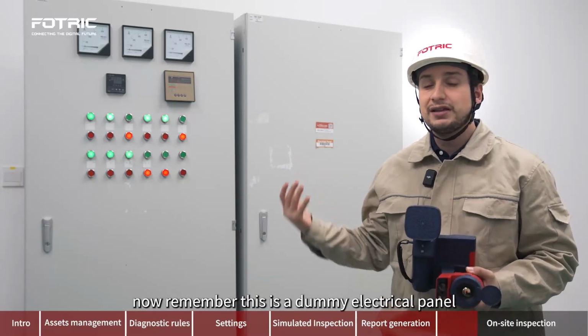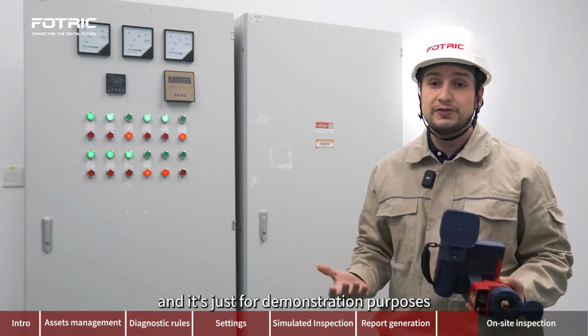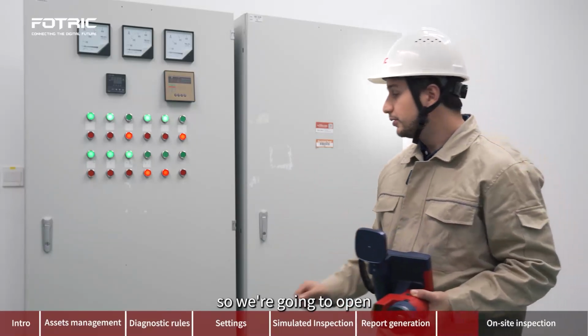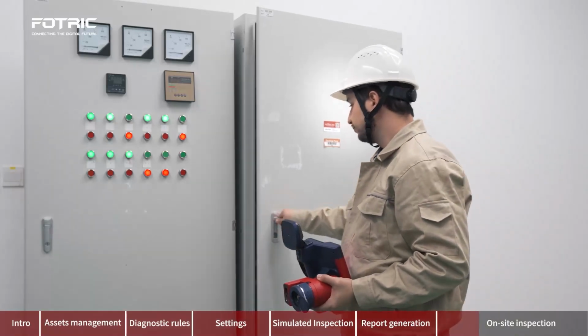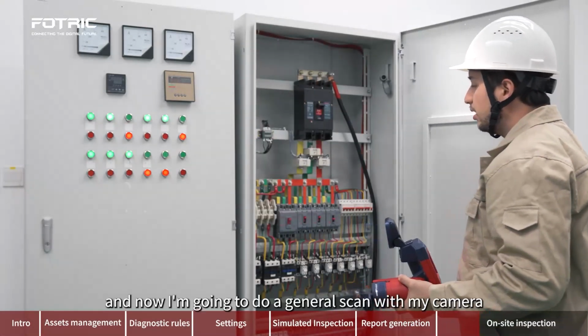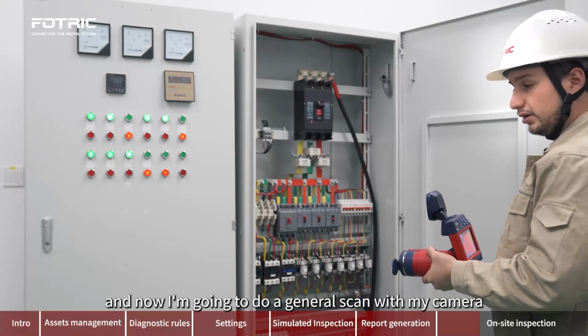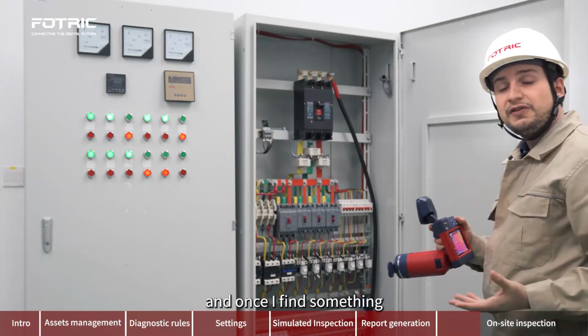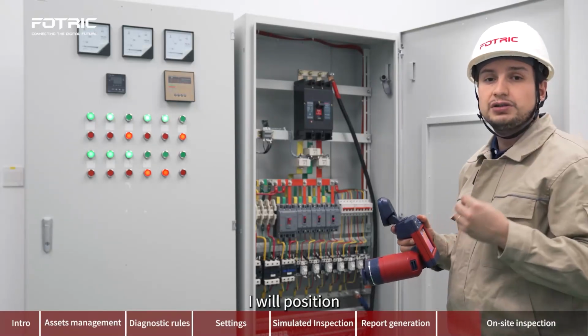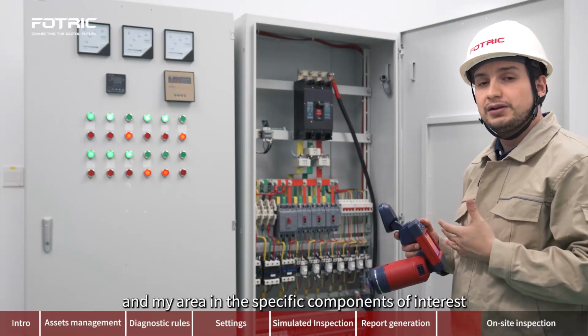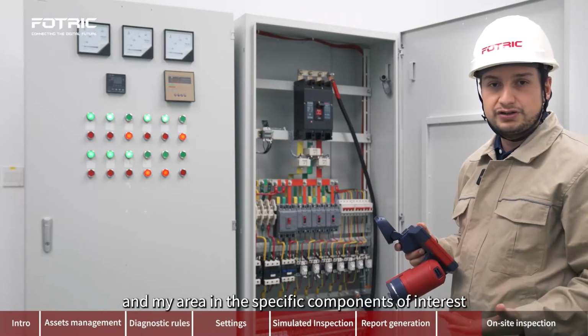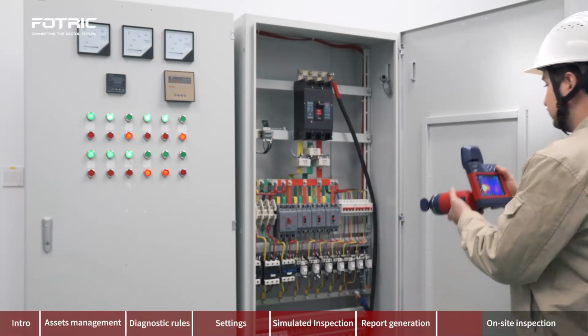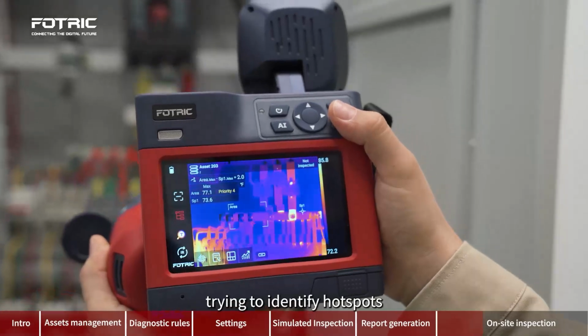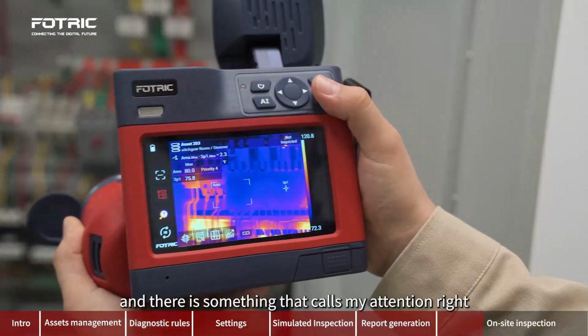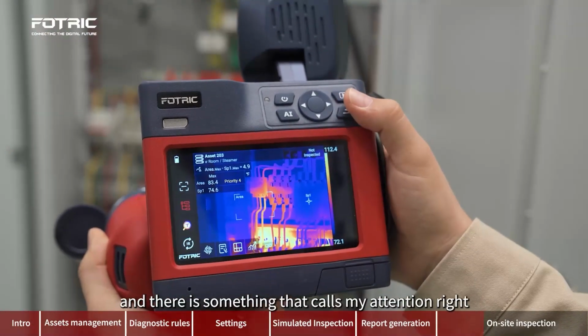Now remember, this is a dummy electrical panel and it's just for demonstration purposes. So we're going to open, and now I'm going to do a general scan with my camera. And once I find something, I will position my reference spot and my area in the specific components of interest. So I'm doing my general scan trying to identify hotspots, and there is something that calls my attention right there.